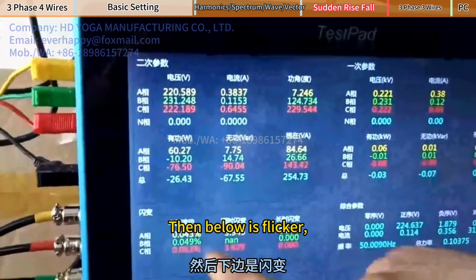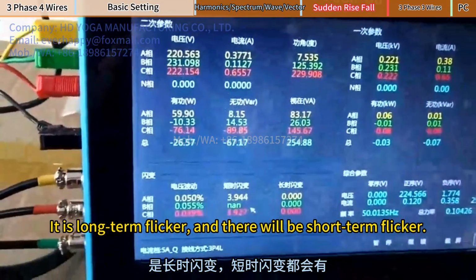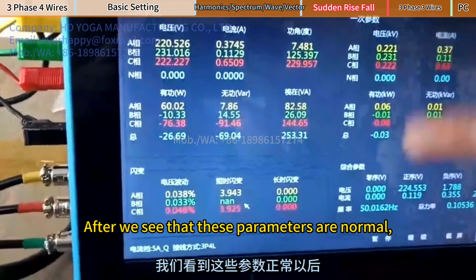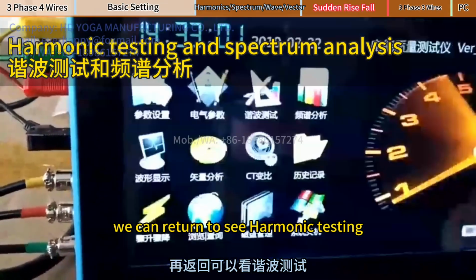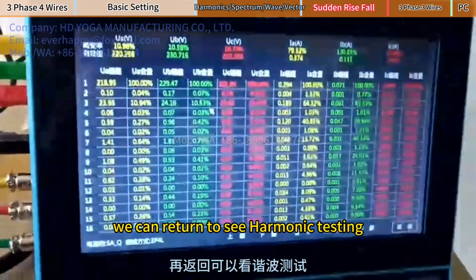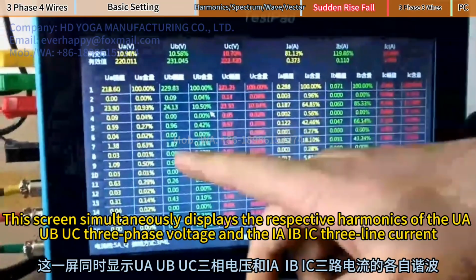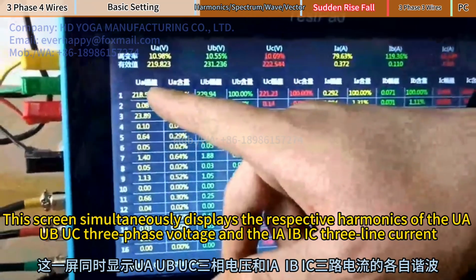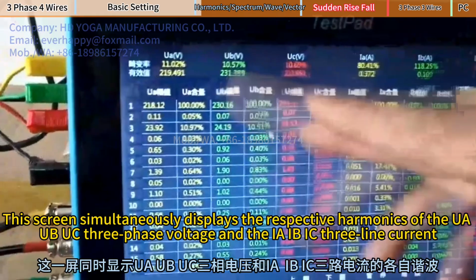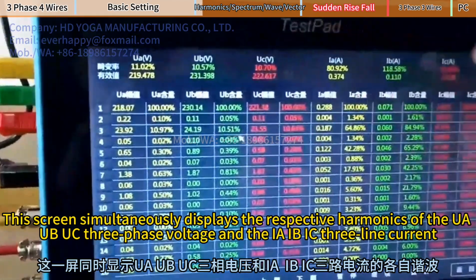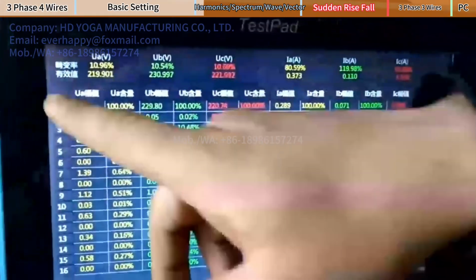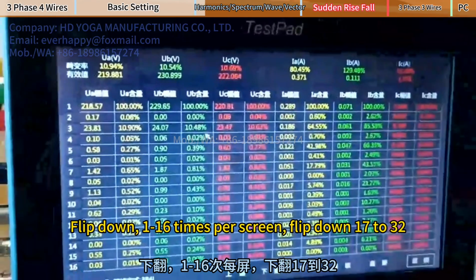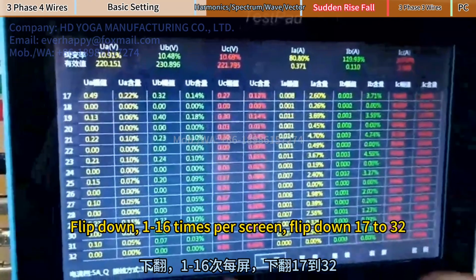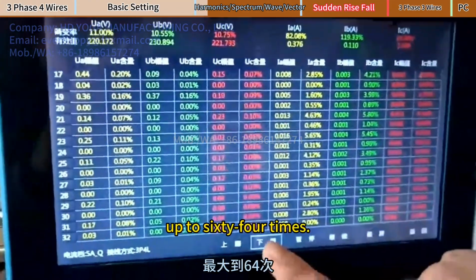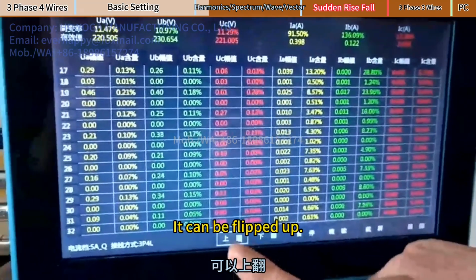Then below is flicker. It is long-term flicker, and there will be short-term flicker. After we see that these parameters are normal, we can return to harmonic testing. Harmonic test. This screen simultaneously displays the respective harmonics of the UA, UB, UC three-phase voltage and the IA, IB, IC three-phase line current. Flip down for 1 to 16 times per screen, flip down for 17 to 32, up to 64 times. It can be flipped up.